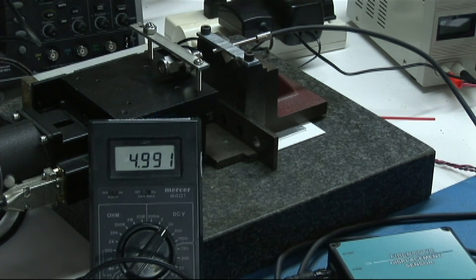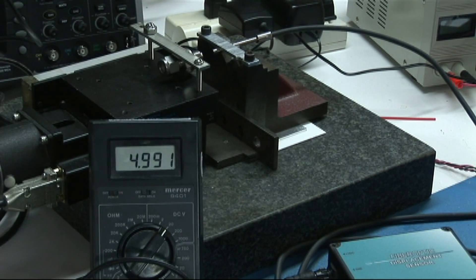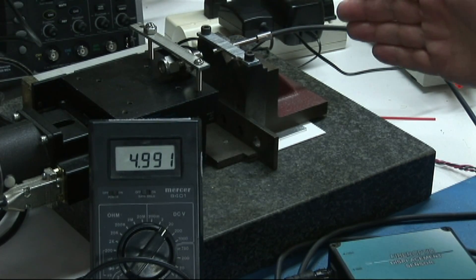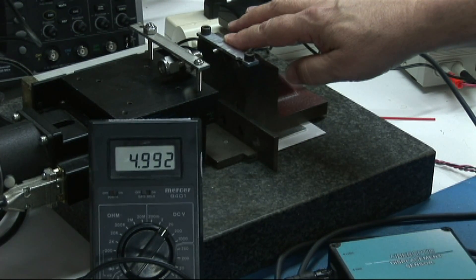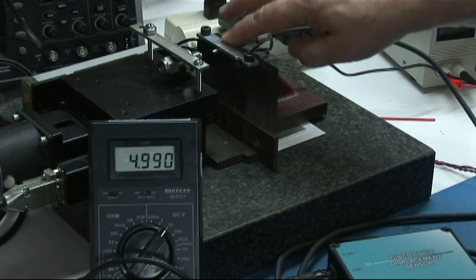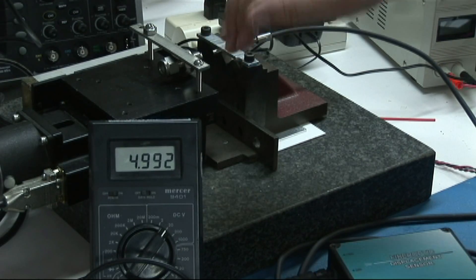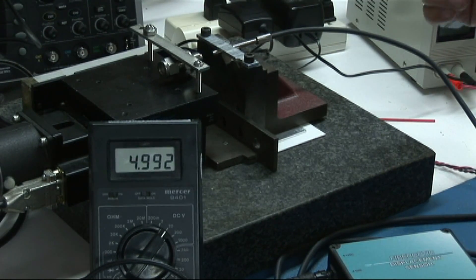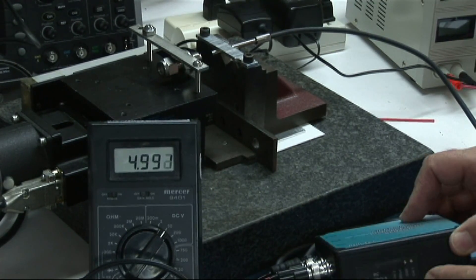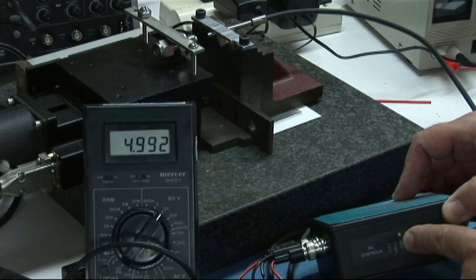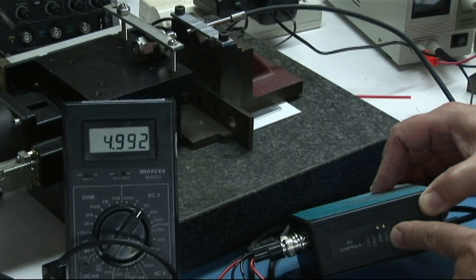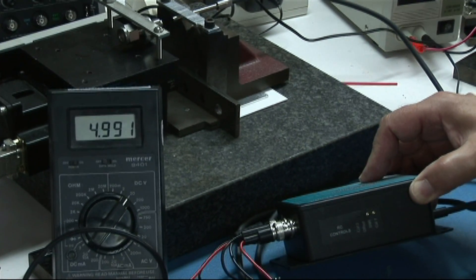So for that reason, we can't duplicate the positioning of the sensors over your pins and the surface of each pin from pin to pin. So I think the best thing for you to do is to go through this procedure where you install your sensor at each pin location, bring it into contact, move a half inch away, and use this Cal-1 control to set the output to exactly five volts, as close to five volts as you could get it. And then you'd be good to go.